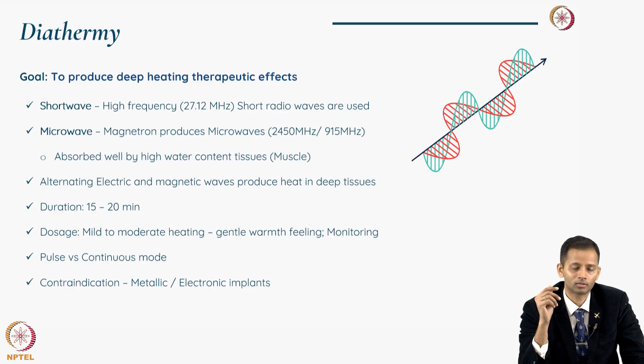Contraindication is that any metallic implant is bound to absorb this heat and hold it within the metal, and that can cause deep burns as well. So it is important, if there is an electronic implant like a cardioverter, that it can malfunction because of the heating. So that needs to be taken into consideration.